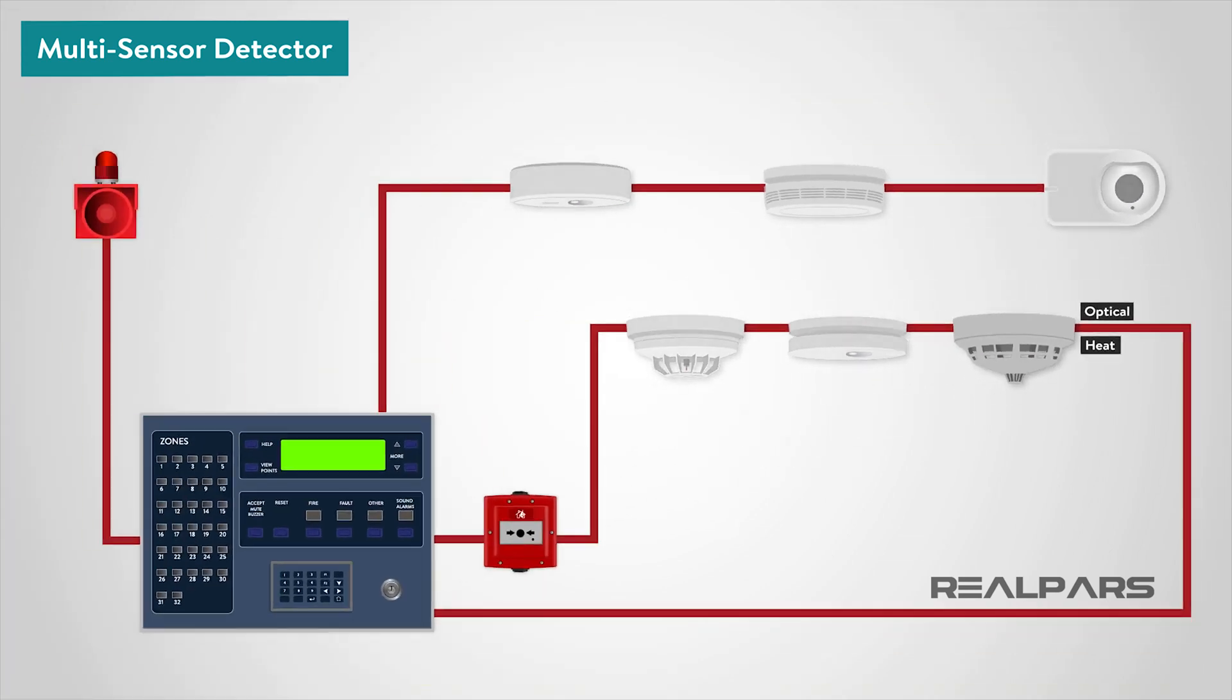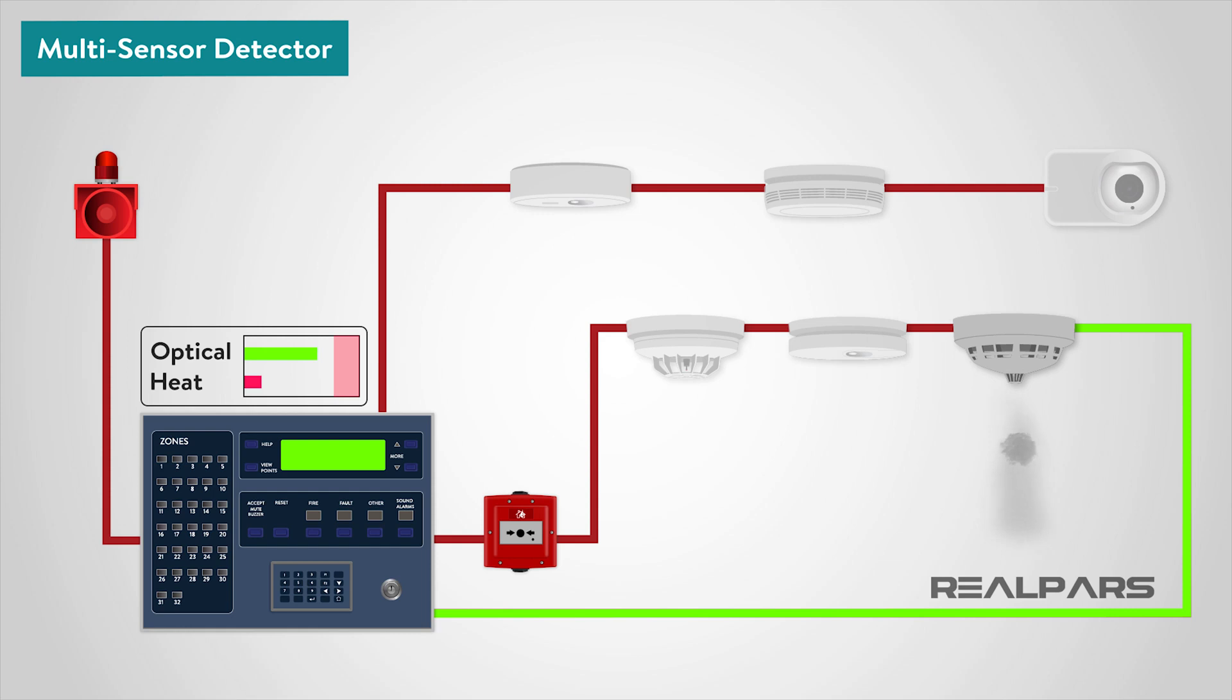When polled by the control panel, the detector returns a value based on the combined responses from both the optical and heat sensors. They are designed to be sensitive to a wide range of fires.